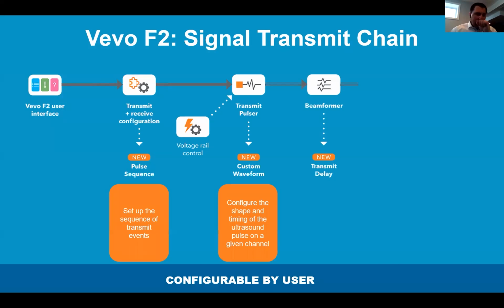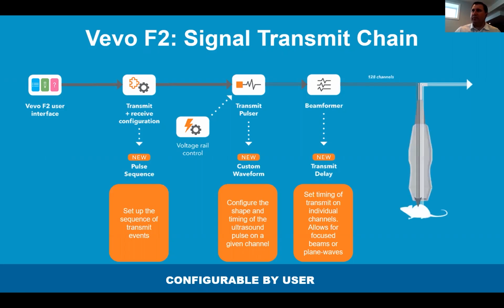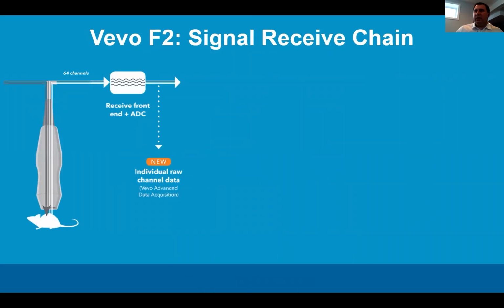From there, we have the ability to set up all of our transmit delays across our transmit beamformer. The timing of individual channels can be set. This allows for the ability to generate focused beams, plane waves, or delay patterns of arbitrary shape. Finally, all of this goes into the transducer, into the imaging subject, and then back. So this is where things get interesting on the receive side. Once those receive channels come back, we have our receive front end and analog to digital converters. This is where we have our new ability to acquire individual raw channel data. This is the so-called VADA point in the signal chain. This allows for offline beamforming approaches to be applied and tested on all of those individual channels.